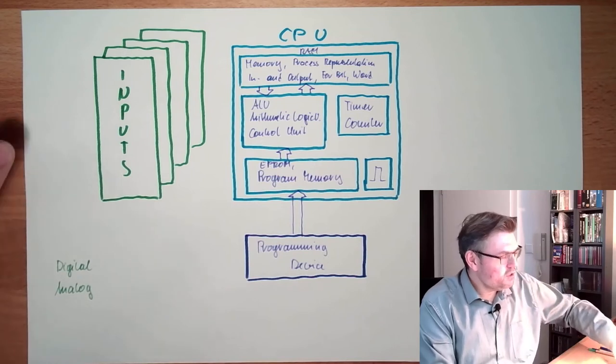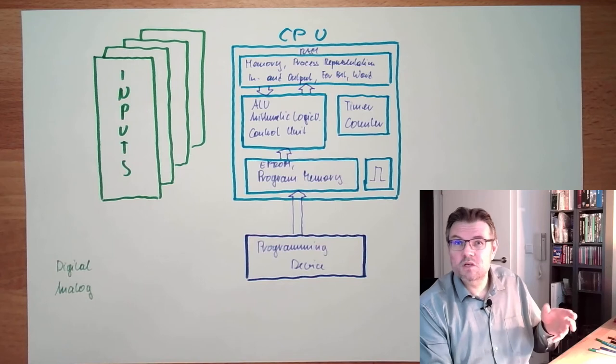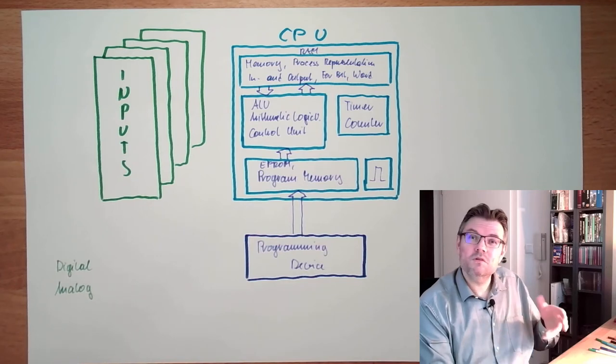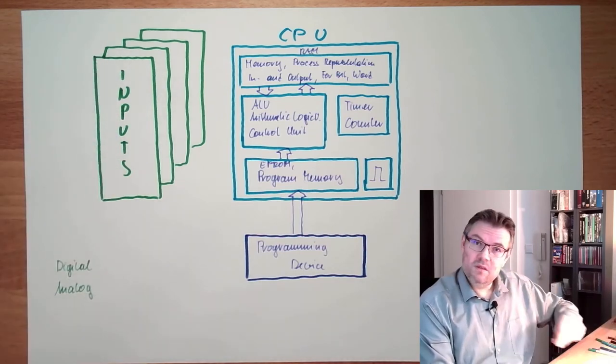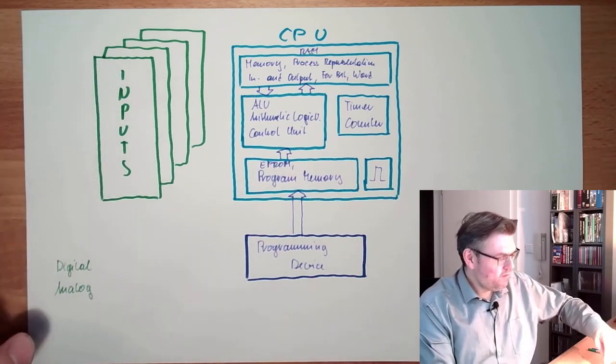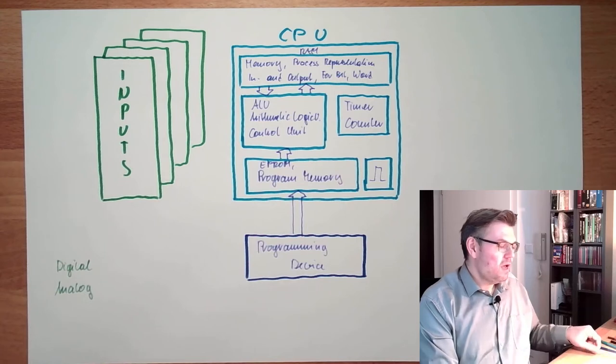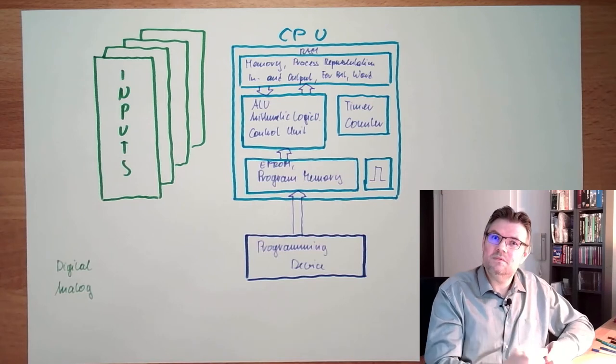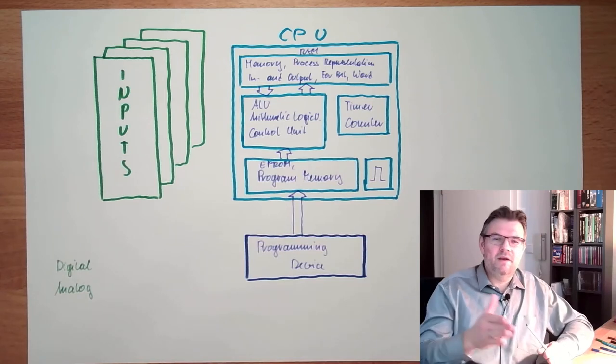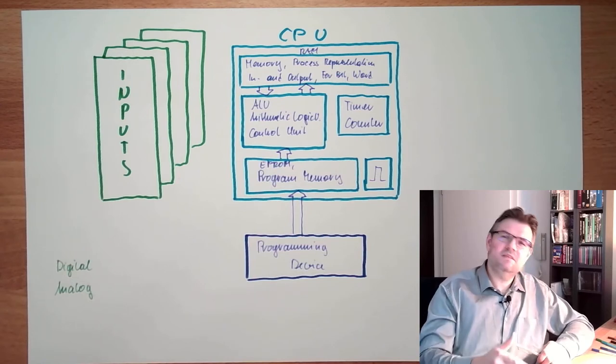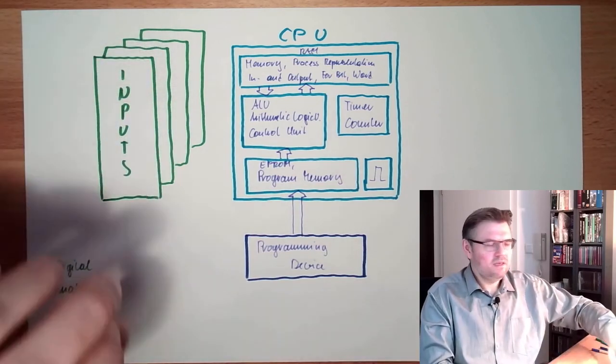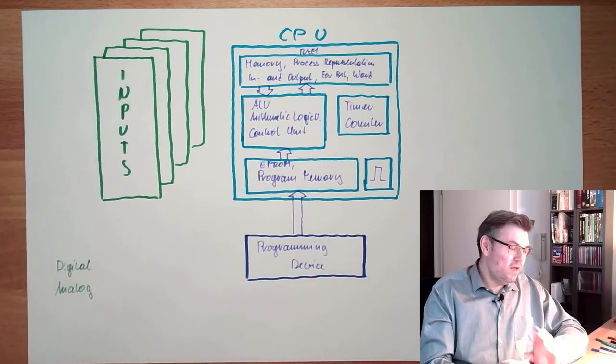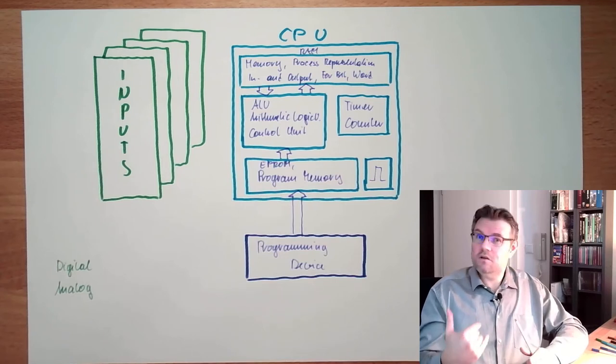Of course, the digital input values must somehow fit the process. So there are inputs of 24V, inputs available of 220V, or something like this. You have to select the correct input card to fit your process voltage level. And there are analog inputs. Analog inputs are usually in standard values. So there is minus 20 to plus 20 milliamps, there is 0 to 10 volts, there is minus 10 to 10 volts, there is 4 to 20 milliamps, something like this. So standard signals are usually supported by those input cards.